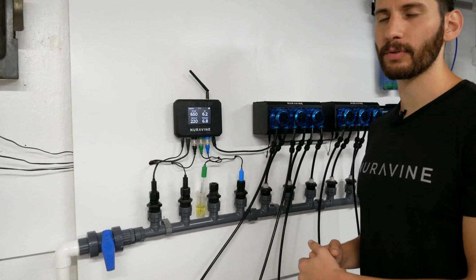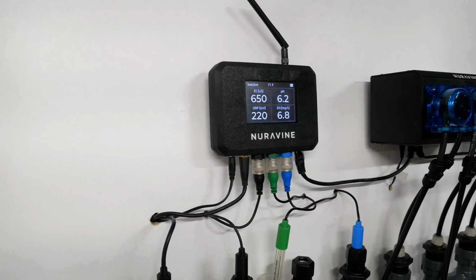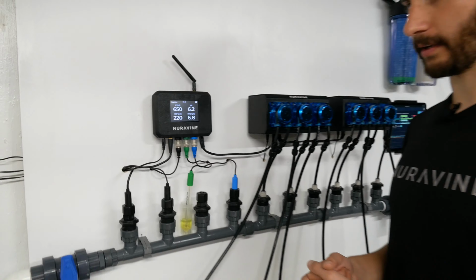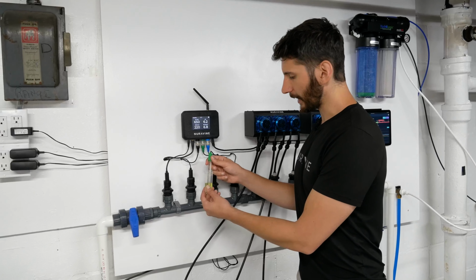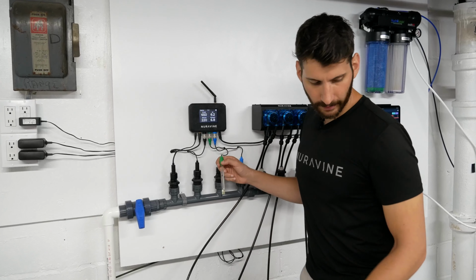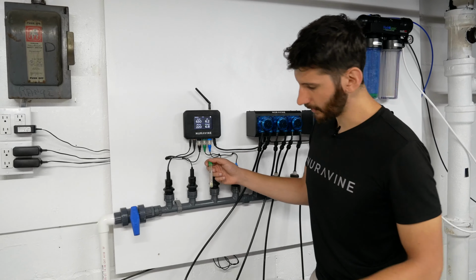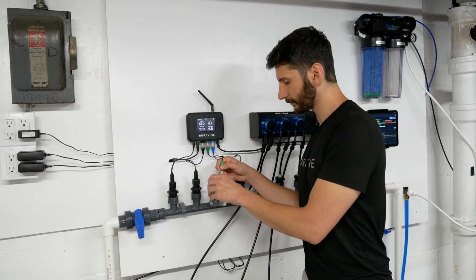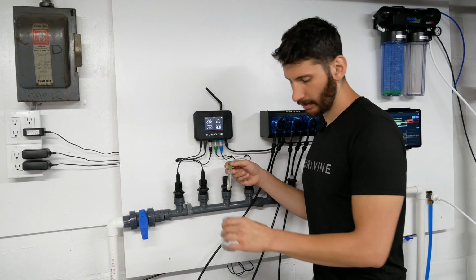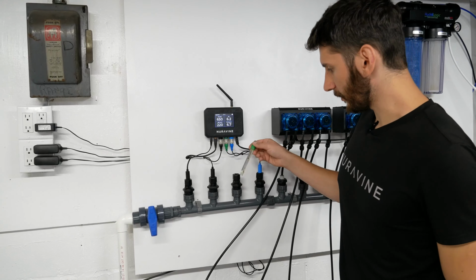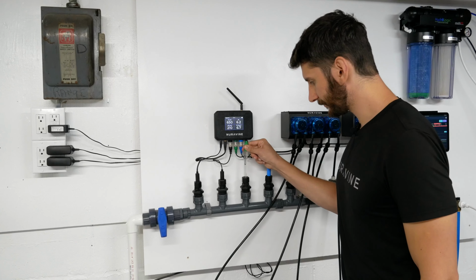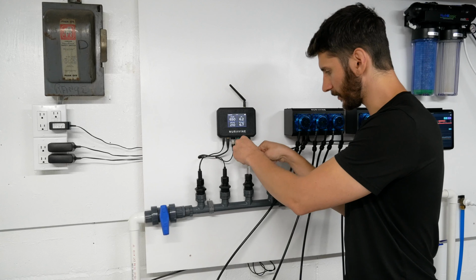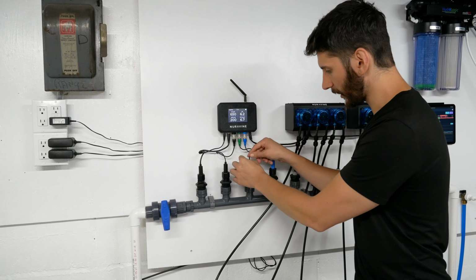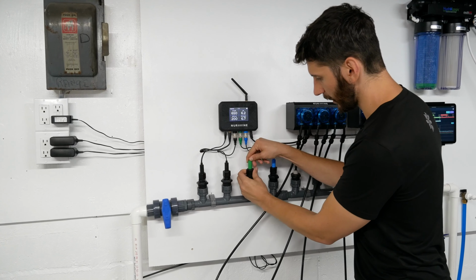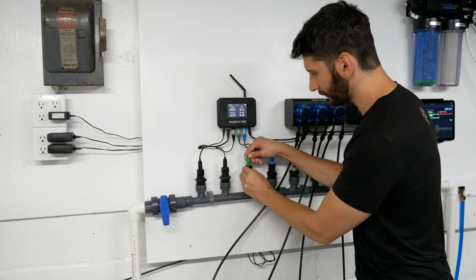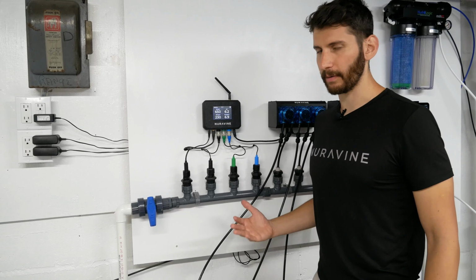So if you get anywhere between 220 and 230, that means the calibration was successful and we can complete the ORP calibration process. Okay, so now we're going to take the probe out of the solution once again, and we're going to give it a little bit of a rinse. And now we can put it back into our manifold. So we're going to slide it right in. Give it a little bit of a twisting motion until it gets to the very bottom, and then we're going to twist our cap, make sure we have a nice tight seal, and then we're done with ORP calibration.